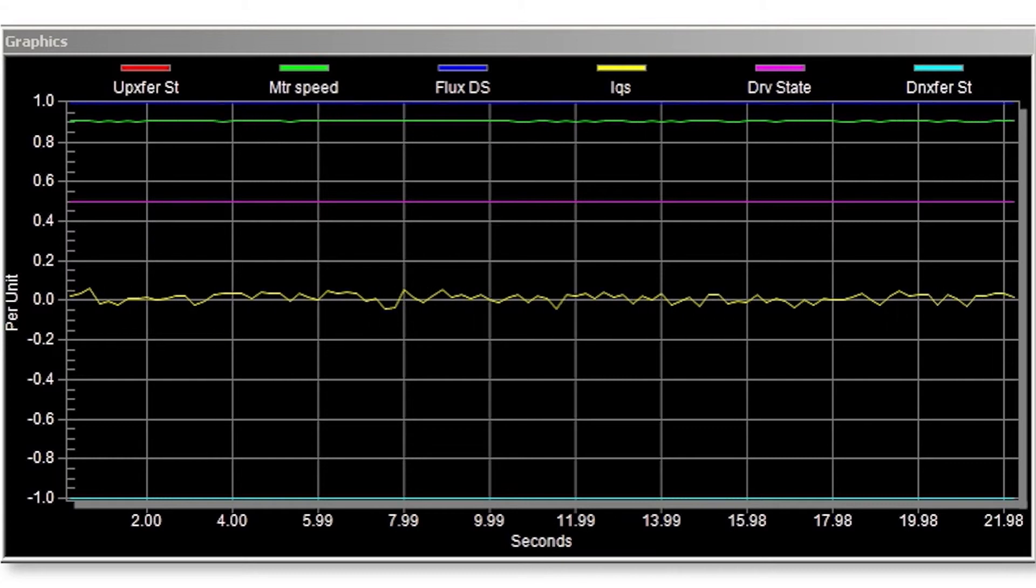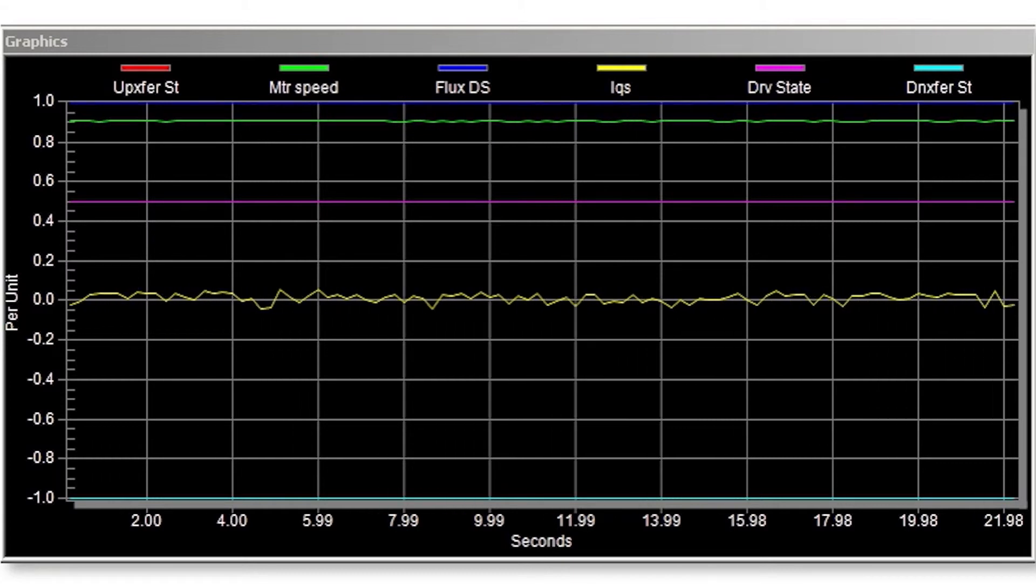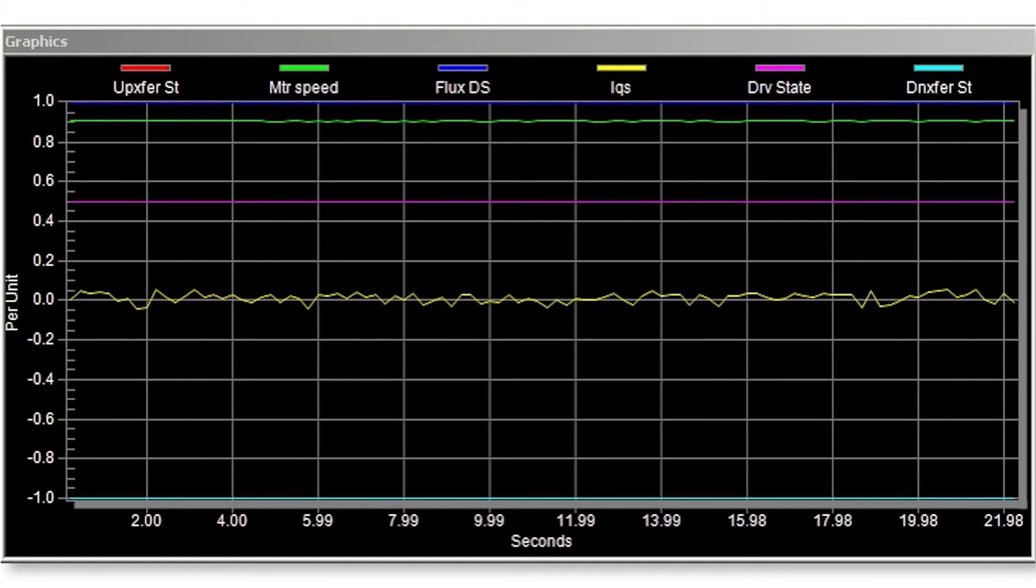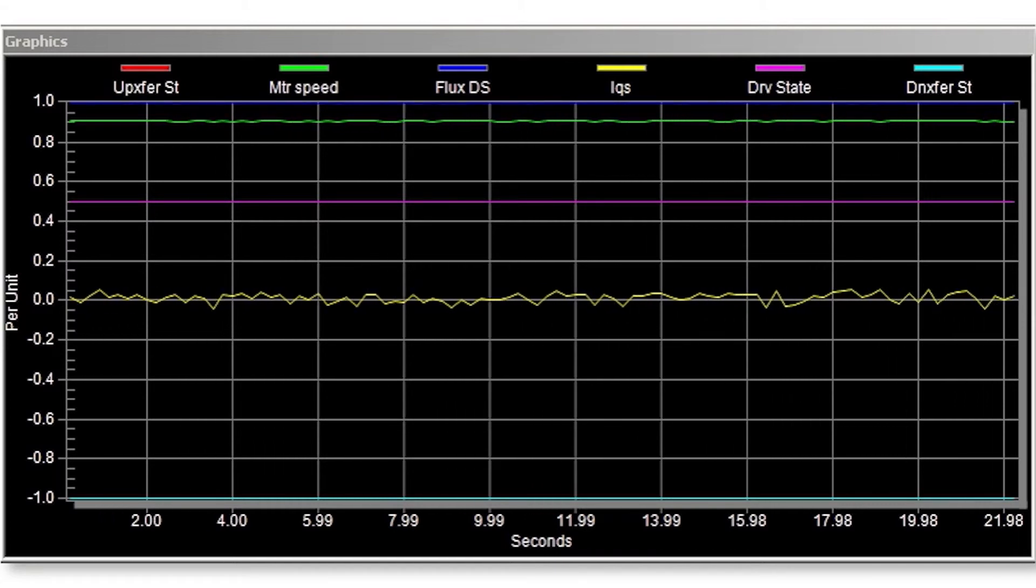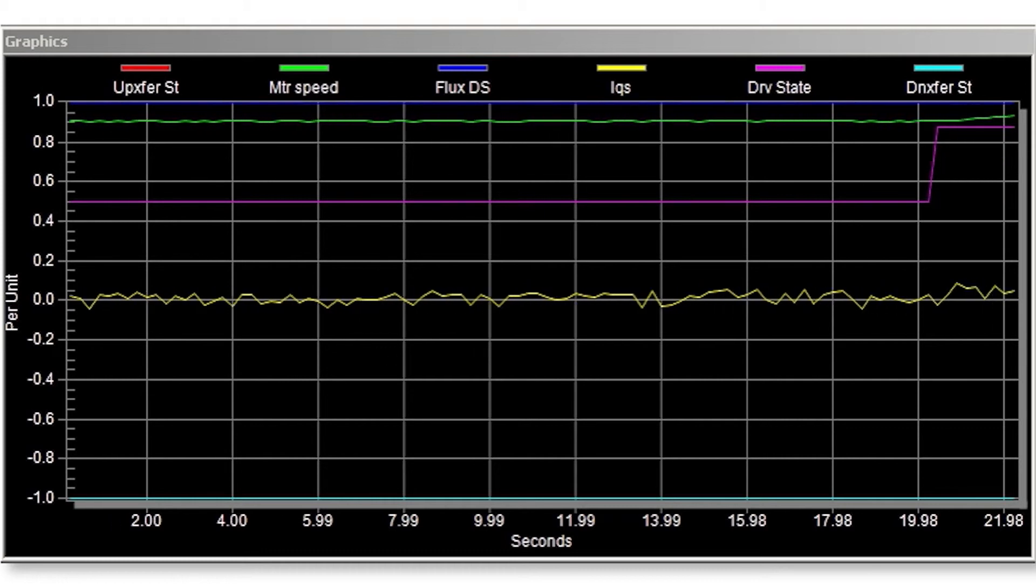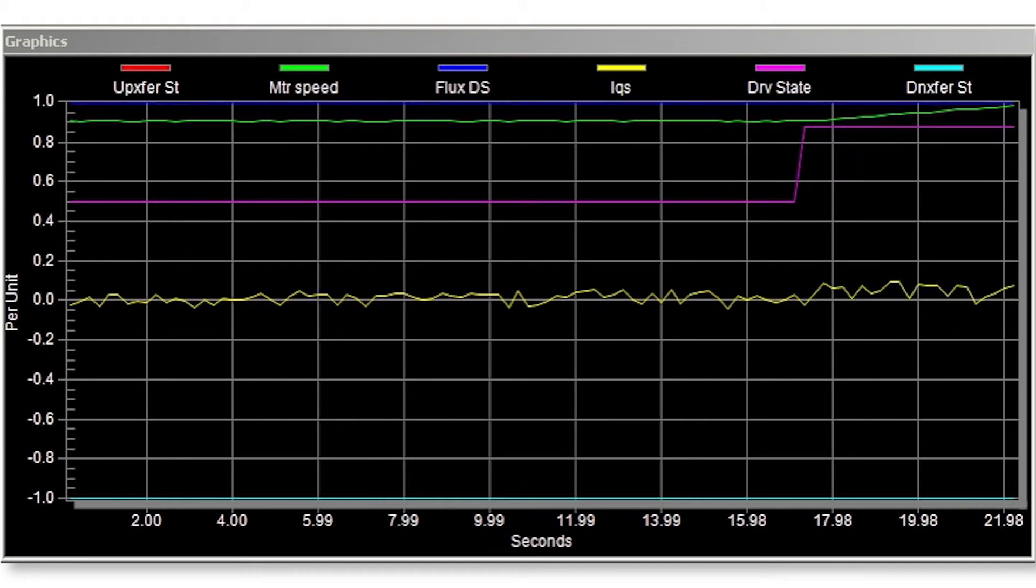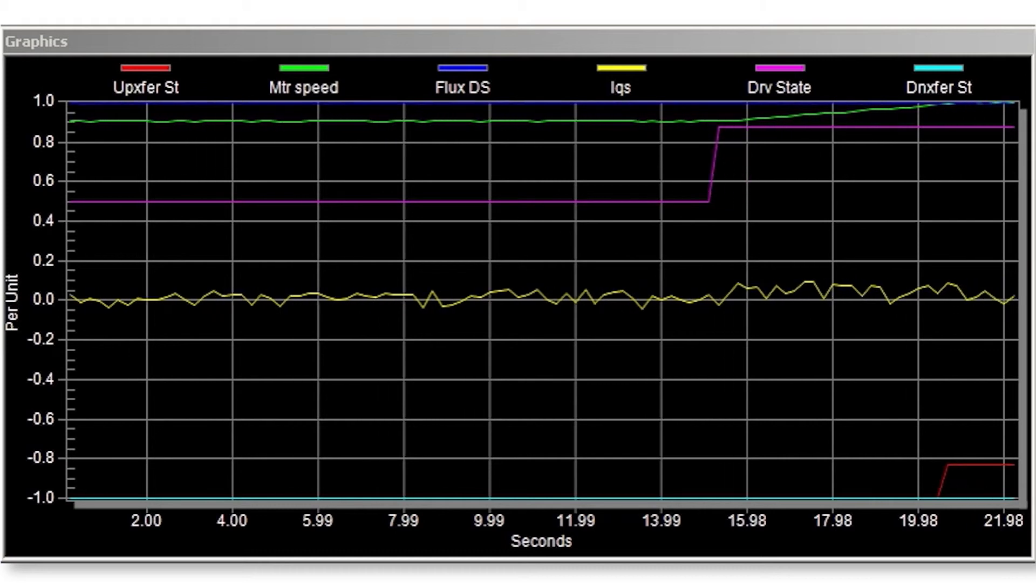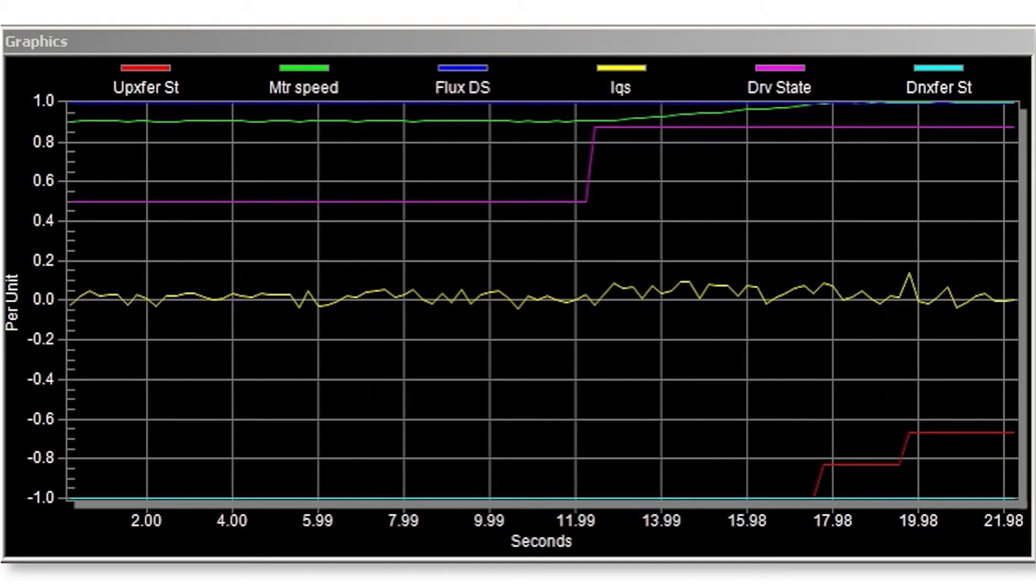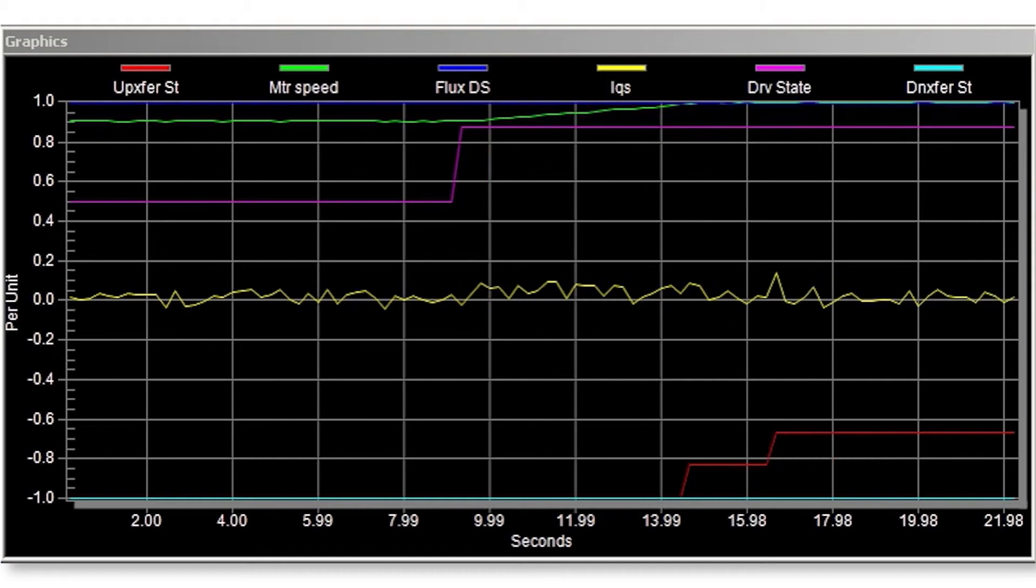The red trace is the up transfer operating state and the green trace represents the motor speed, which is being run at approximately 90% rated speed. The drive is given an up transfer request as shown by the rising edge of the purple trace from run state to up transfer. The VFD output accelerates the motor to 100% line frequency and achieves phase and frequency lock at 60 Hz.